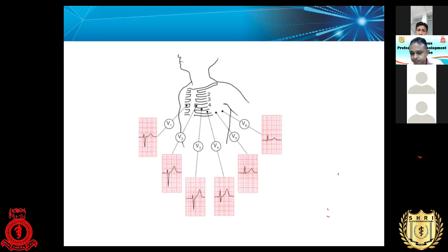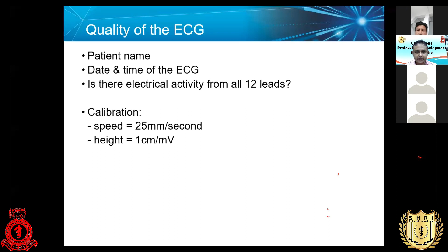And document the name, age, the date and time of the ECG that you have taken, and check whether all the 12 leads are recorded properly. And your machine has to be calibrated at 25 millimeters per second, the speed, and the height should be calibrated at 1 centimeter per millivolt. If you change these, we will get abnormal ECGs, which are pseudo abnormalities that we are going to record. So make sure that your calibration is correct with the speed at 25 millimeters per second and the height is at 1 centimeter per millivolt.